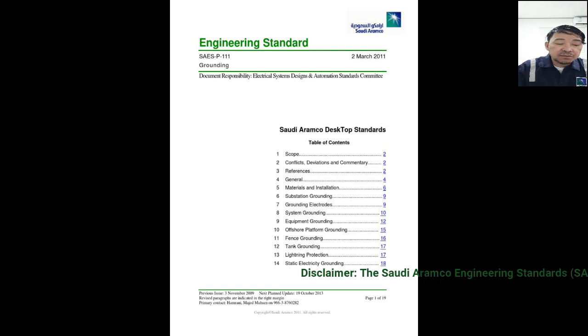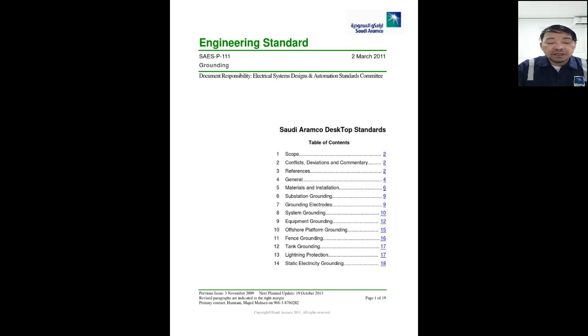As per SAES-P-111 5.6, grounding conductors extending through concrete or asphalt shall be run in PVC conduit, which is the preferred one, or PVC coated rigid steel conduit. And as per SAES-P-111 paragraph 5.7, underground ground conductors shall be insulated when within 3 meters of a buried metal pipeline or metal piping.